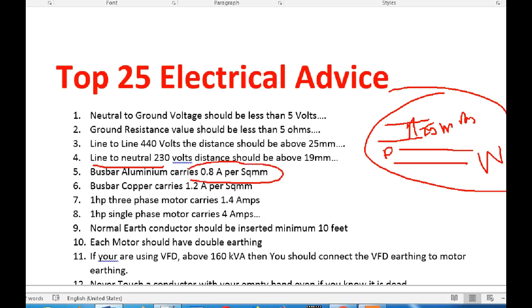If you have an aluminum bar, it will be 1mm square and it will carry 0.8A. For example, if you have an aluminum bar with a size of 100mm by 10mm, that gives you 1000mm square. In 1000mm square, the current will be 0.8A per mm squared. If we have that size, it will carry 800A, so we have to use the appropriate size.